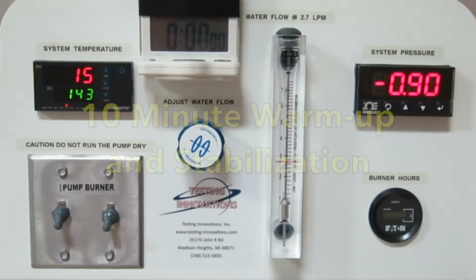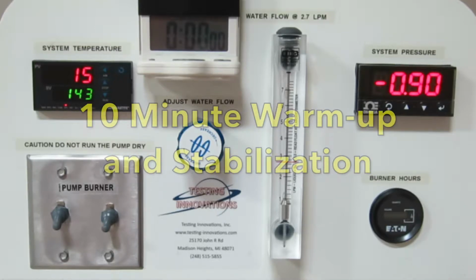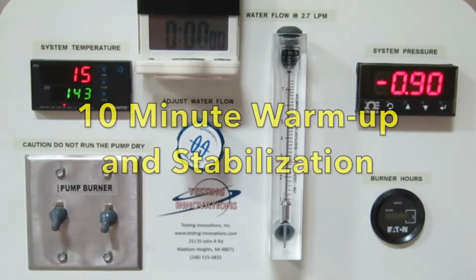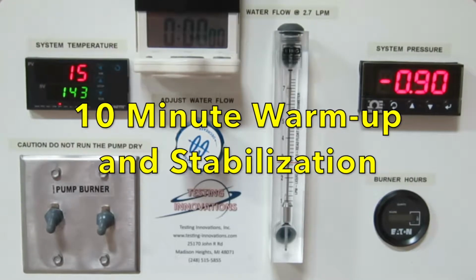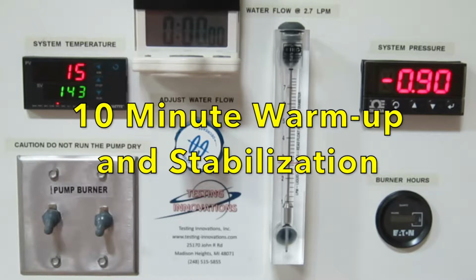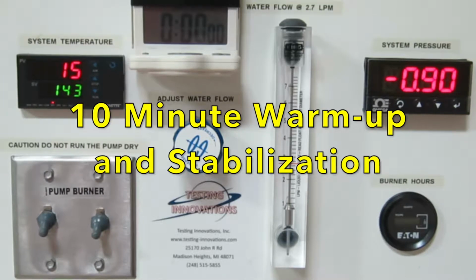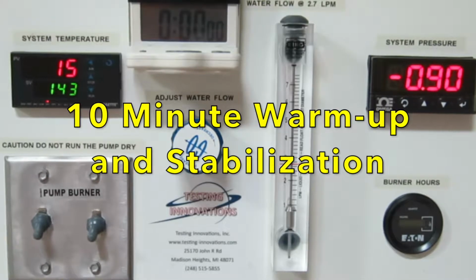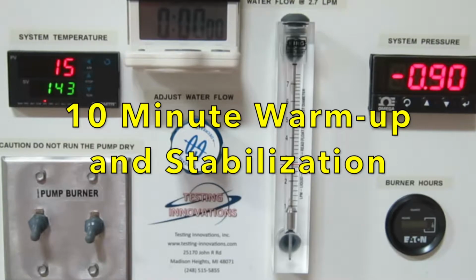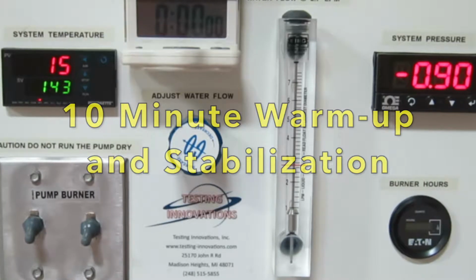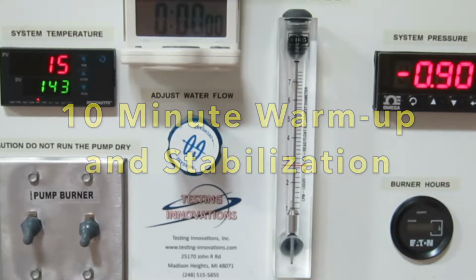During this 10-minute video, you will be watching the normal machine warm-up and stabilization prior to the calibration verification. Every time you use this machine, you will need to verify the calibration. This process is also known as the calibrate upon use phase. We have noticed that running the pump initially for a period of time before turning on the burner stabilizes the temperature of the incoming water. Doing this before initializing the burner leads to fewer adjustments after the warm-up and stabilization period that is being shown next. Ideally, you would like to see ground temperature water going into the machine.